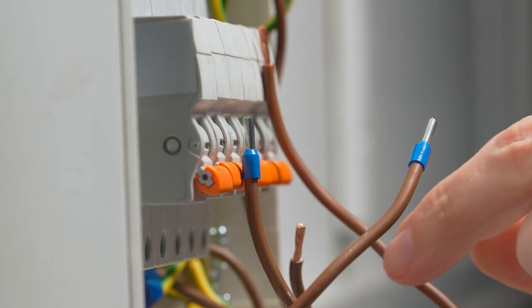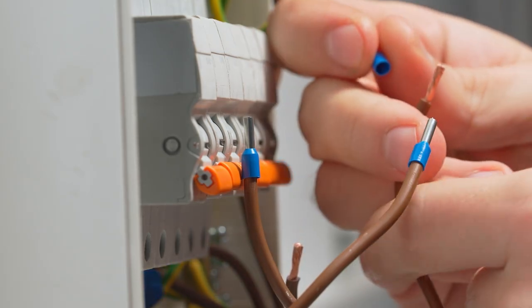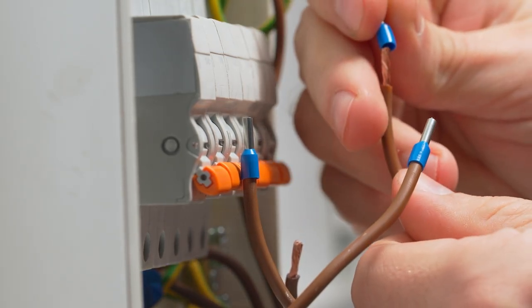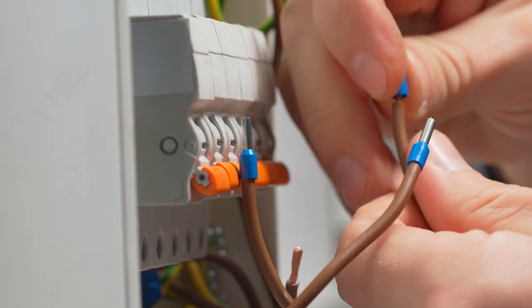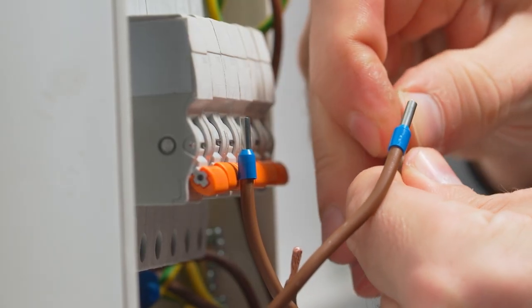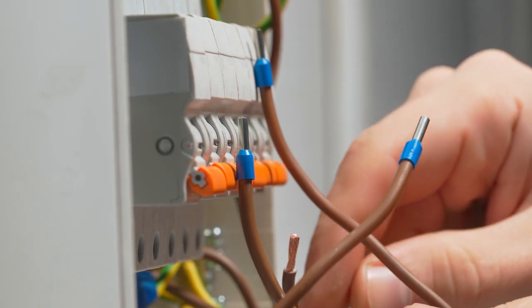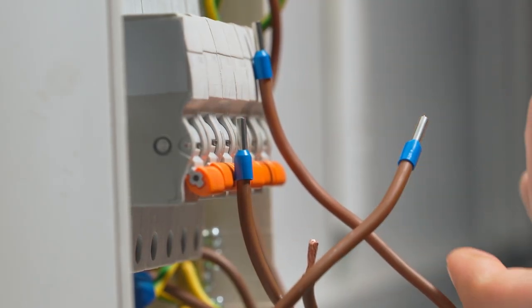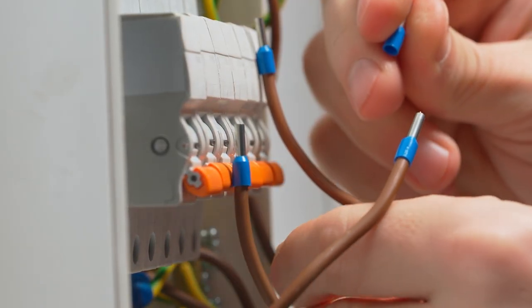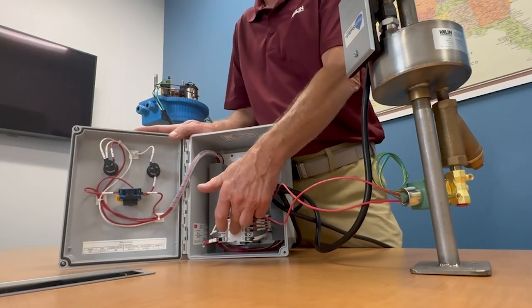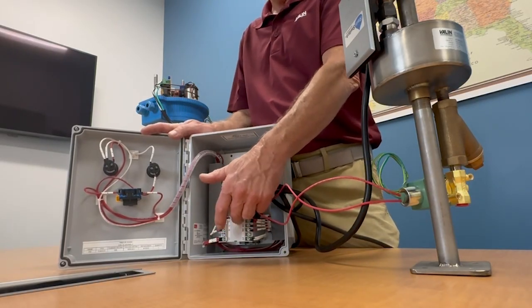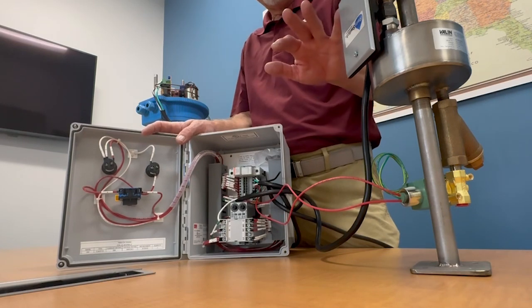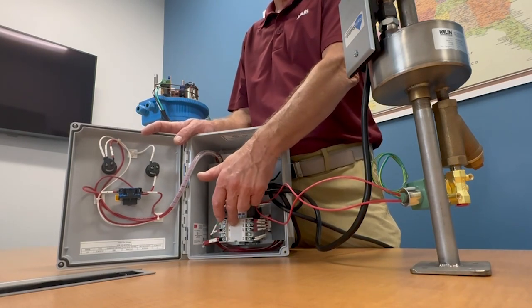The level relay that we provide supplies 120 volts to the rain switch probe, though it is restricted to nanoamps. Therefore, it is UL approved. It's safe. It'll not shock anybody, and that's the purpose of having this level relay. If a different relay is used, you will be putting 120 volts on the probe, and it'll potentially electrocute somebody.